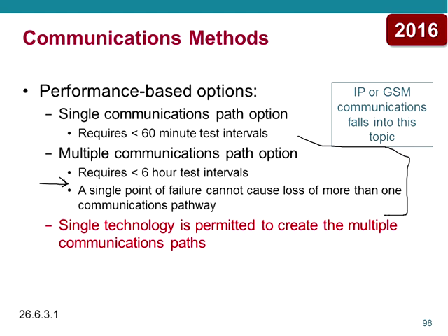That way, again, the risk is evaluated with this one and with this one. And you'll see with this one, a single pathway, within an hour, I have to get a trouble. Within this one, it's within 6 hours, but I have multiple pathways. So the risk is essentially the same, but if you have multiples and you lose more than one, it can't cause the loss of the other, or the other pathways.